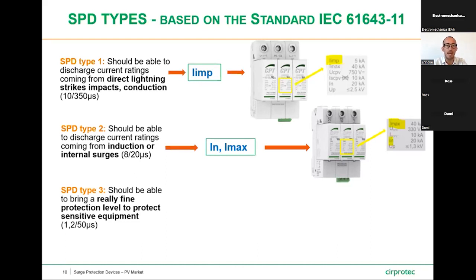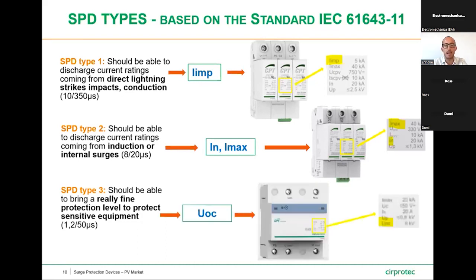The SPD type 3 should be able to bring a really fine protection level to protect sensitive equipment connected to our installation. These SPD type 3 are tested under a specific waveform named 1.2/50 microseconds. The parameter belonging to the SPDs type 3 is the Uoc.